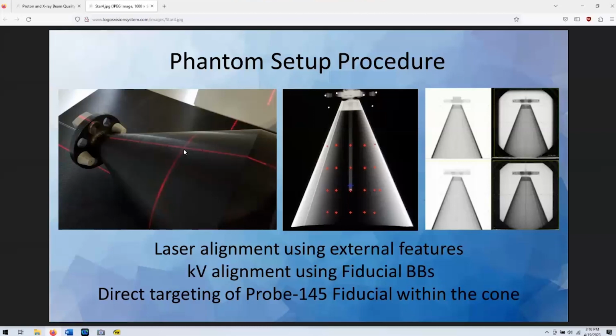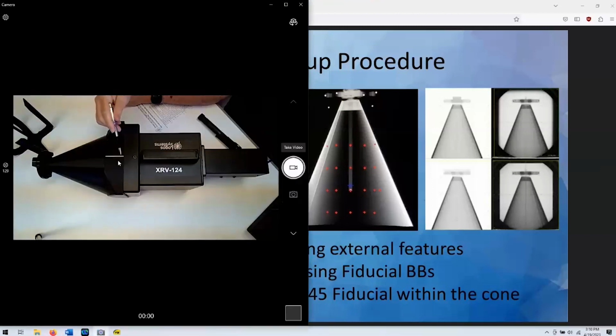Advanced users will want to use beam diameter measurements captured during star shot metrology. Shooting directly at the Pro BB will cause a shadow in the exit spot, which affects beam measurements. Shooting off axis so that the beam is closer to reference hole G is a useful solution. Delivering multiple energies at each gantry angle yields volumes of useful data from the typical 12-angle, 30-degree star shot. BeamWorks Delta enables users to quickly extract single-energy star shot folders from a multi-energy star shot dataset.